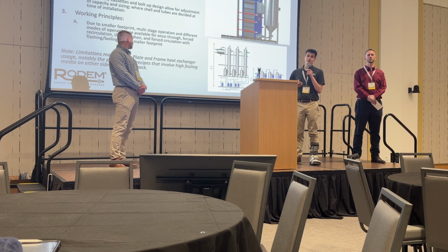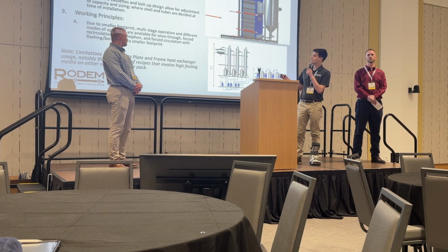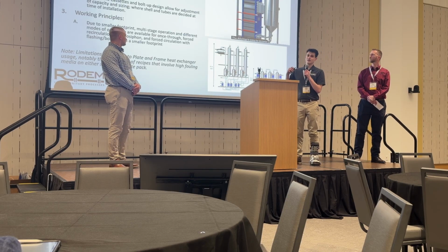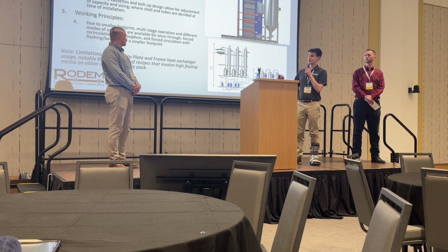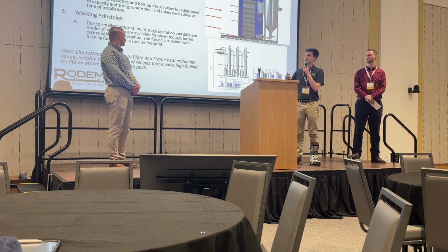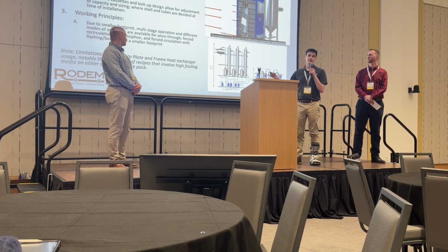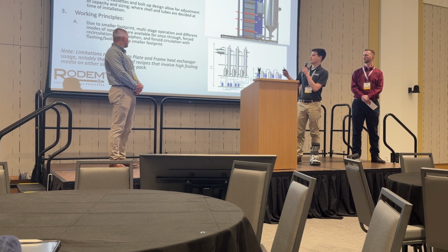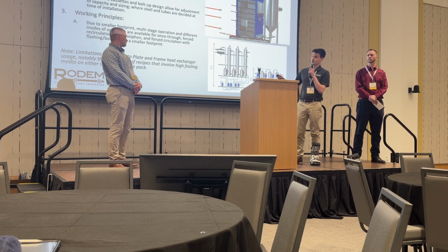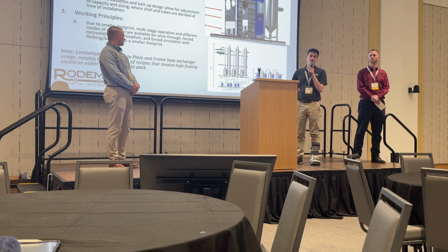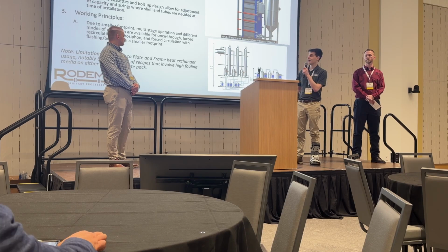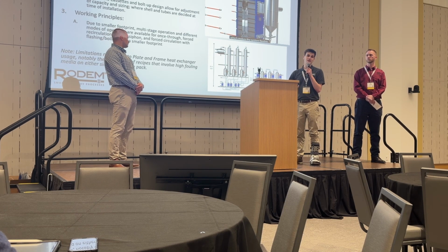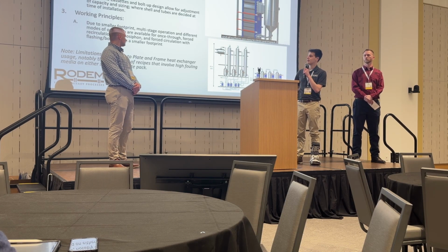So we've heard about some falling film evaporators, but some advantages of doing a plate and frame style evaporator, as shown in the top right, is that there's less fouling typically and it's easier to do maintenance on, instead of having a rigid heat exchanger. The ability to change the capacity if you have changes in your process or usage. And then the overall footprint of the system. If you look in the bottom right, you'll see it can be as small as 50% of the falling film evaporator style. And just with the orientation, which I'll touch on later, you don't always need a recirculation pump to circulate the fluid inside.